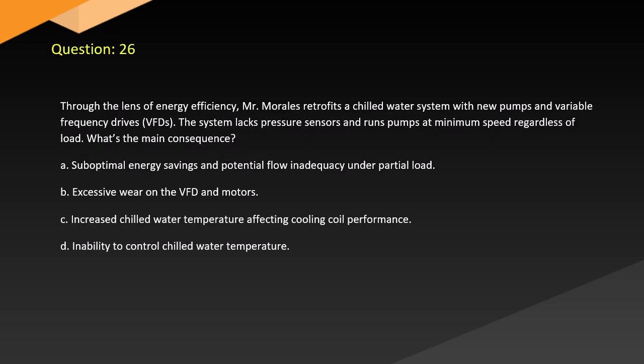Question 26. Through the lens of energy efficiency, Mr. Morales retrofits a chilled water system with new pumps and variable frequency drives, VFDs. The system lacks pressure sensors and runs pumps at minimum speed regardless of load. What's the main consequence? A. Suboptimal energy savings and potential flow inadequacy under partial load. B. Excessive wear on the VFD and motors. C. Increased chilled water temperature affecting cooling coil performance. D. Inability to control chilled water temperature.